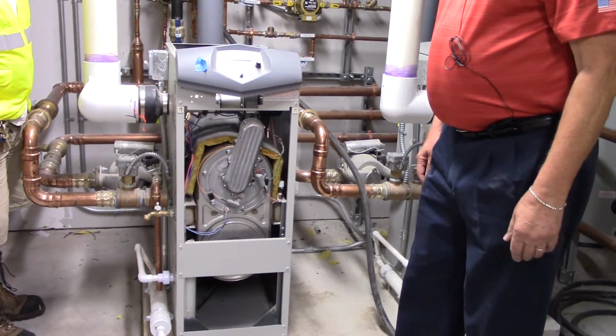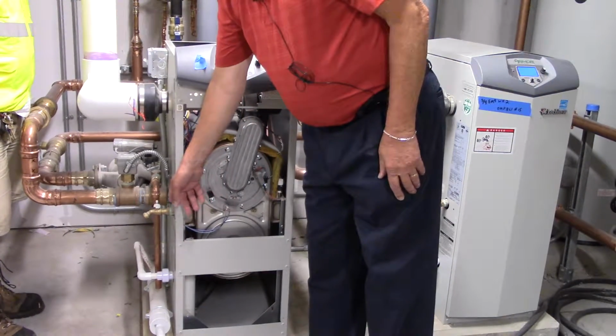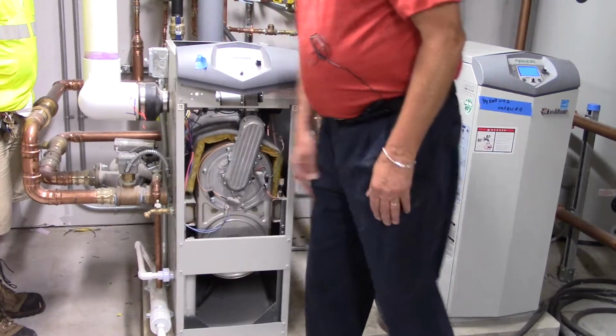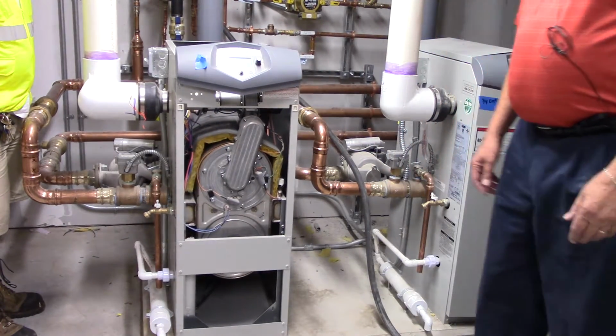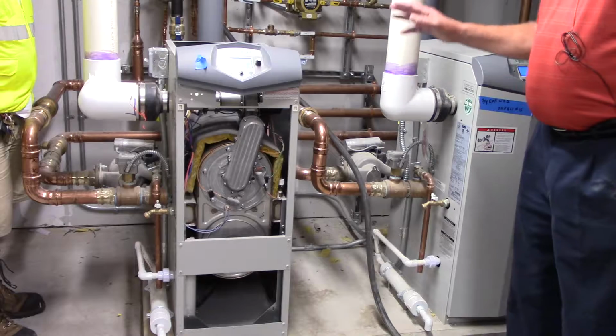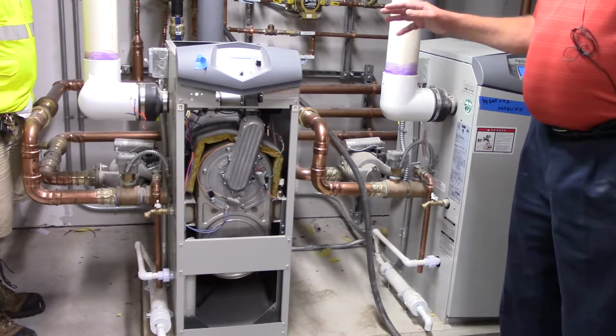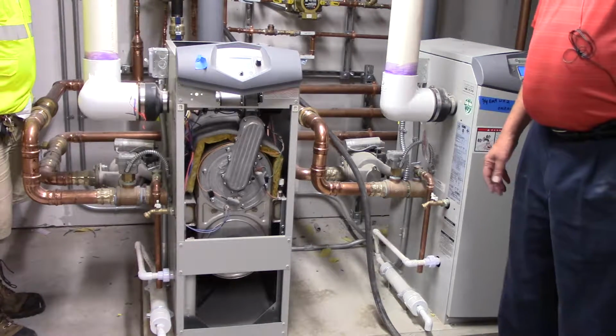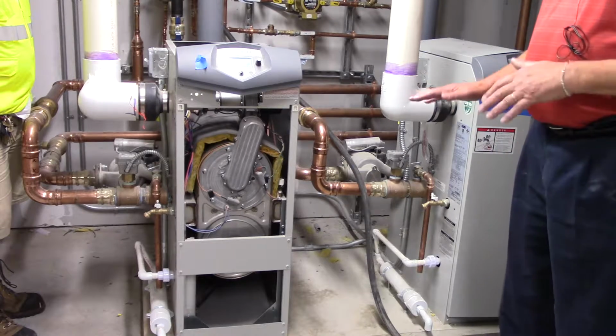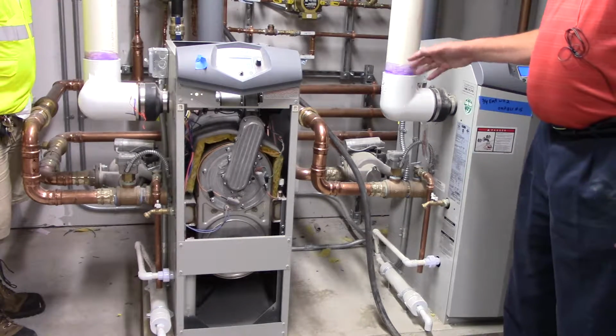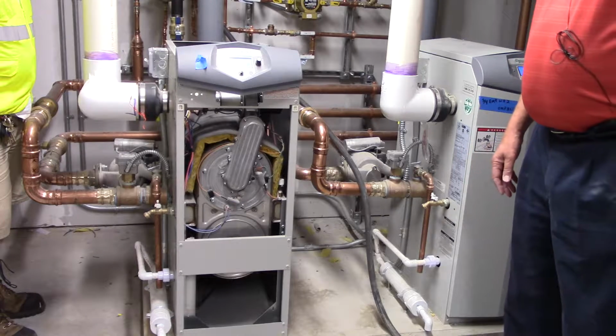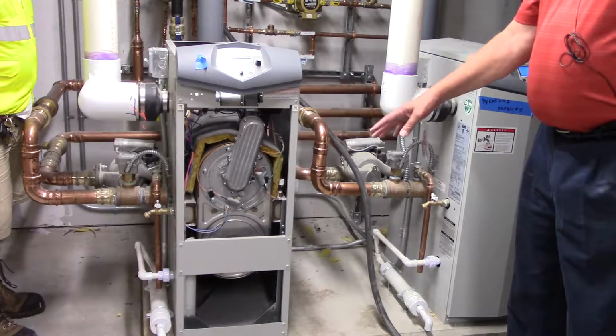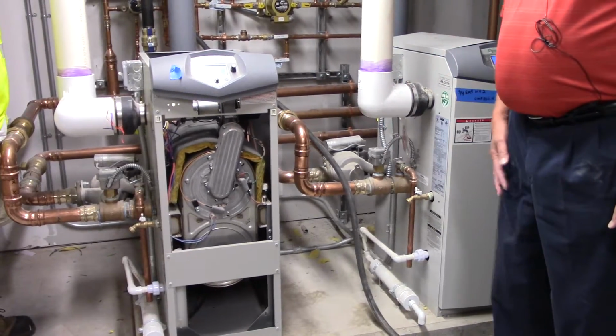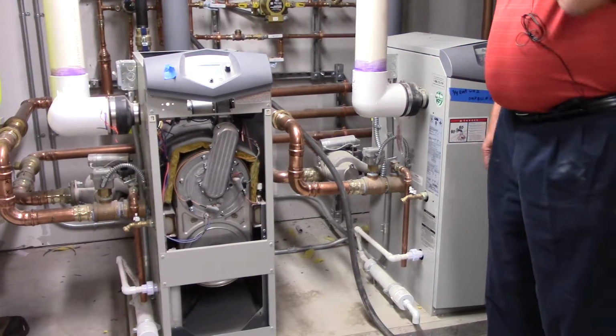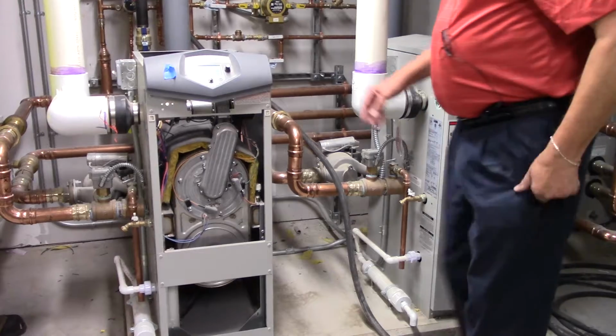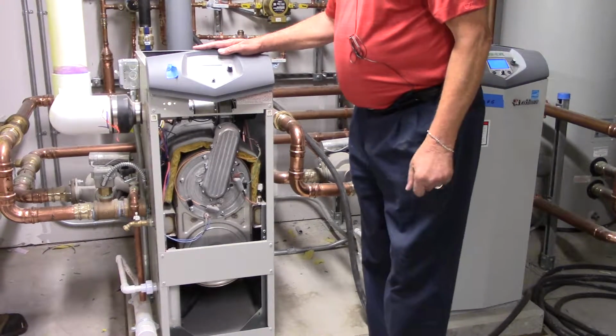Okay. Each of these units is equipped with a condensate neutralizer. That neutralizer should probably be recharged twice a year. These will do up to 3 gallons, 3.5 gallons an hour of condensate when they're in full condensing mode, which they're going to be 99% of the time. So you want to pay attention to that, because if you're not treating the condensate, it will eat that drain up.